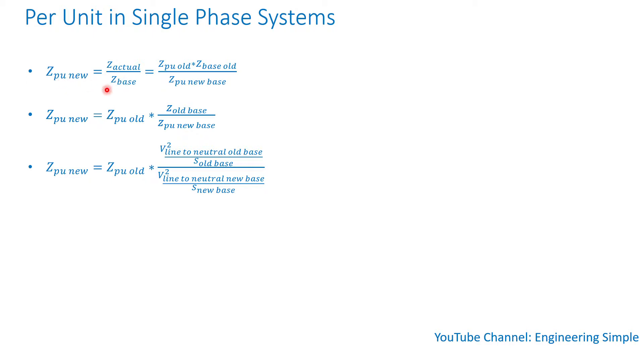If you have a per unit impedance and want to convert it to a new base — for instance, when you buy a transformer — the impedance might be 5%, or 0.05 per unit, but it's calculated on, say, 700 MVA. When you include it in a power system using a 100 MVA base, you have to convert that 5% from the 700 MVA base to the 100 MVA base.